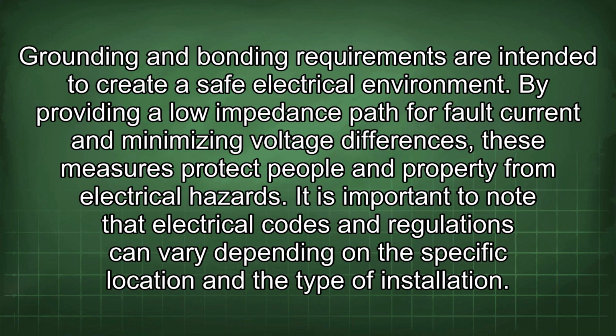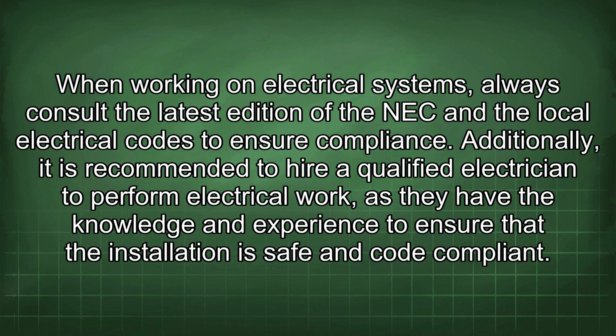Grounding and bonding requirements are intended to create a safe electrical environment. By providing a low impedance path for fault current and minimizing voltage differences, these measures protect people and property from electrical hazards. It is important to note that electrical codes and regulations can vary depending on the specific location and the type of installation. When working on electrical systems, always consult the latest edition of the NEC and the local electrical codes to ensure compliance. Additionally, it is recommended to hire a qualified electrician to perform electrical work, as they have the knowledge and experience to ensure that the installation is safe and code compliant.